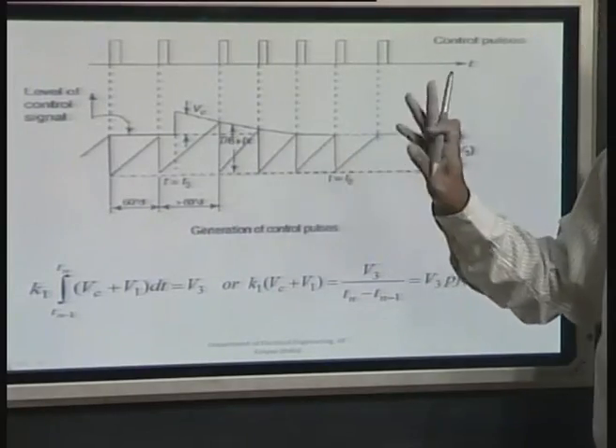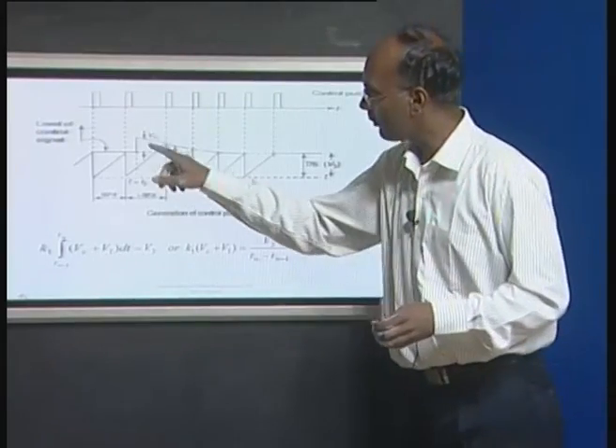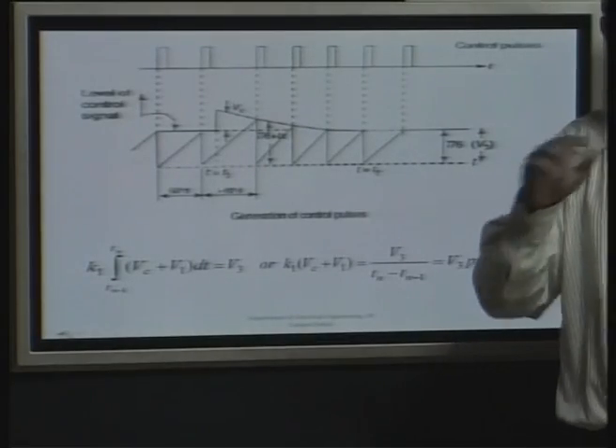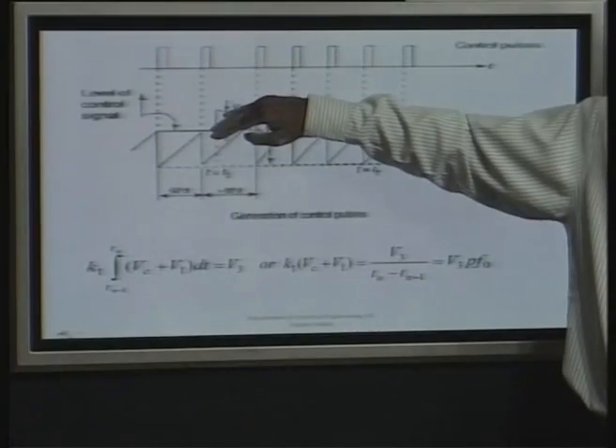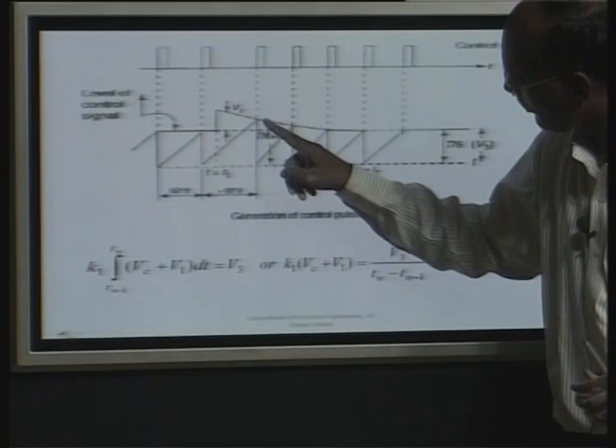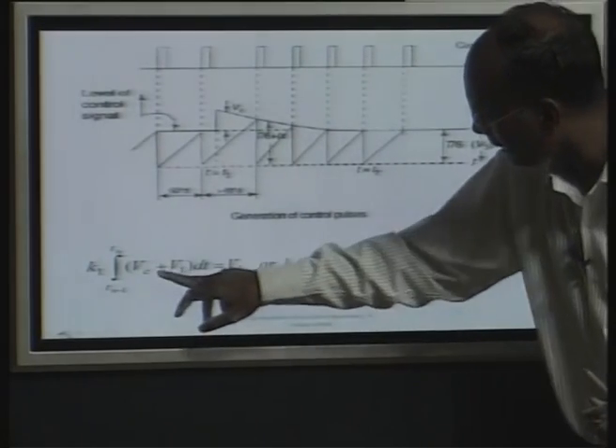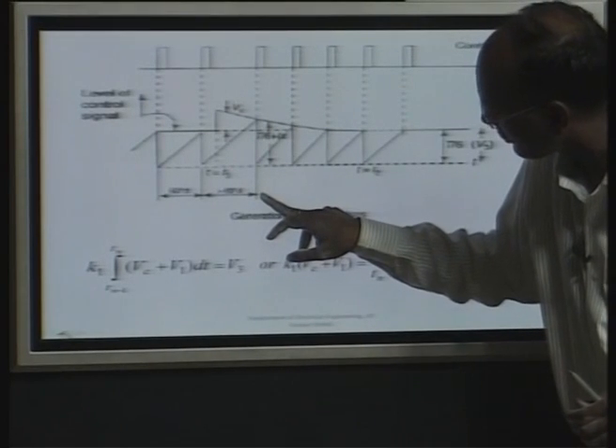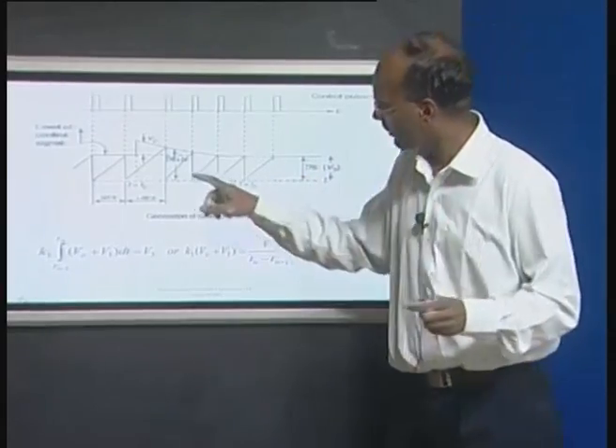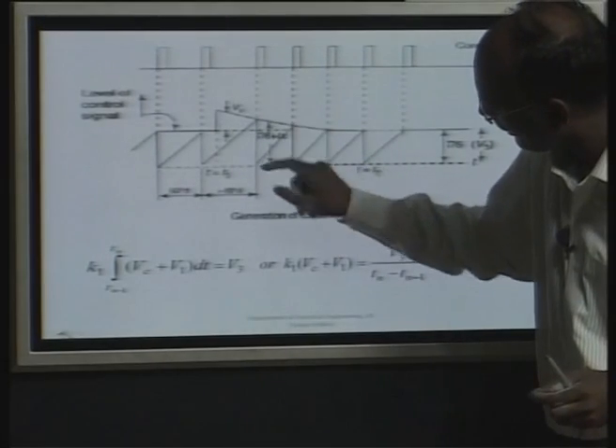Looking at the pulse generation: V₃ is compared with the ramp. When V_C is zero, the VCO generates a ramp circuit and when V₃ is reached, the pulse is generated normally at 60-degree intervals. If there is error and V_C has some positive value, the ramp increases faster (V₁ + V_C is added), so the ramp reaches V₃ sooner than 60 degrees — meaning this interval is reduced below 60 degrees, advancing the firing pulse, which changes the alpha accordingly.